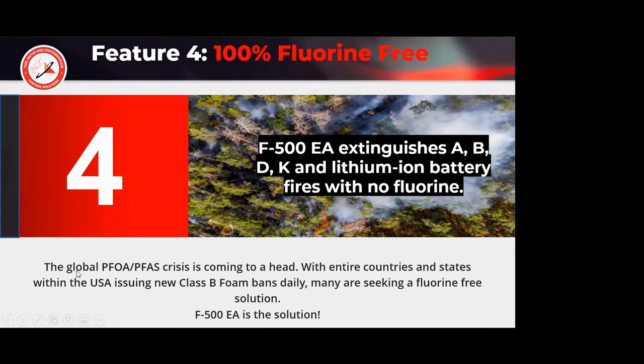This leads into the global PFOA, PFAS crisis coming to a head. Entire countries and US states are issuing foam bans on Class B foams, and many fire departments are seeking fluorine-free solutions. The problem is that fluorine-free foams require three times the application density of fluorinated foam, so you're applying three times as much, and they cost more. So for a fire department moving from a banned fluorinated foam to a fluorine-free foam, their cost goes up by a factor of 6 to 10.